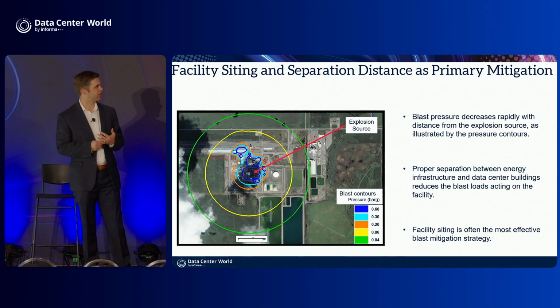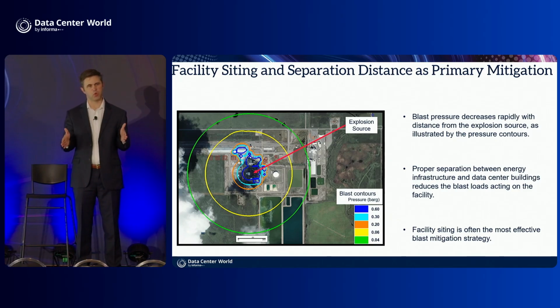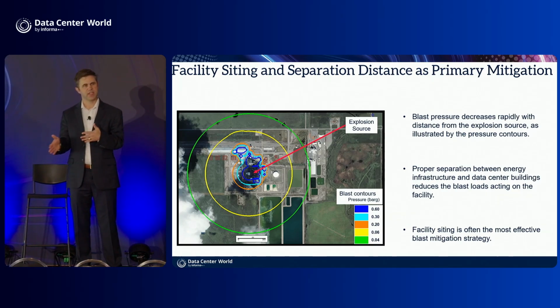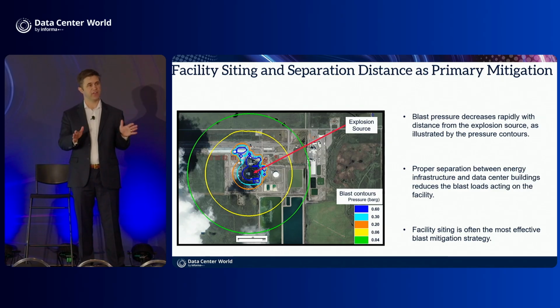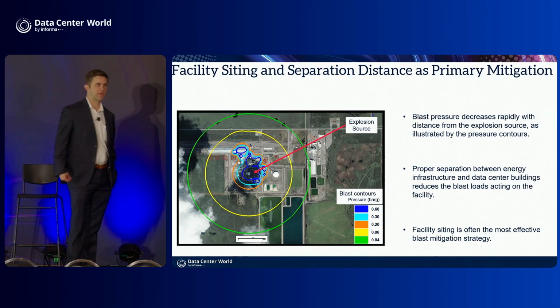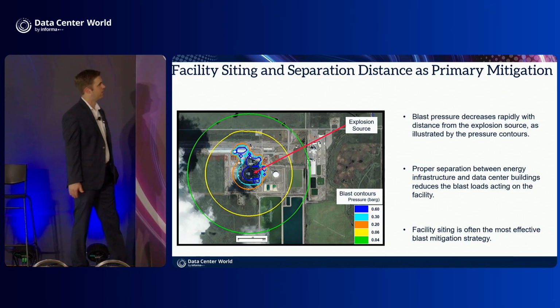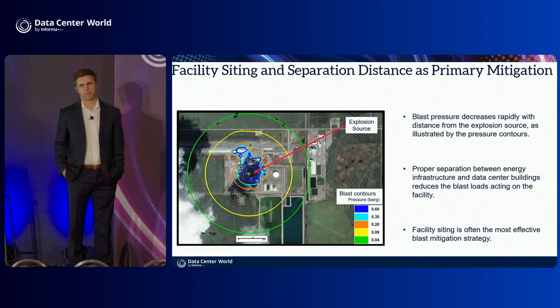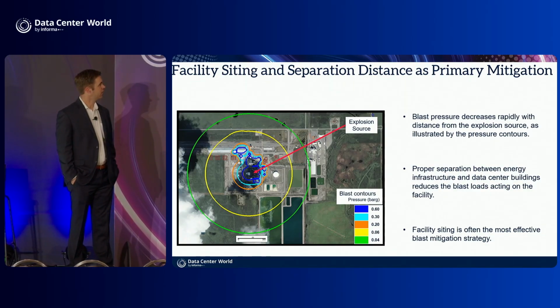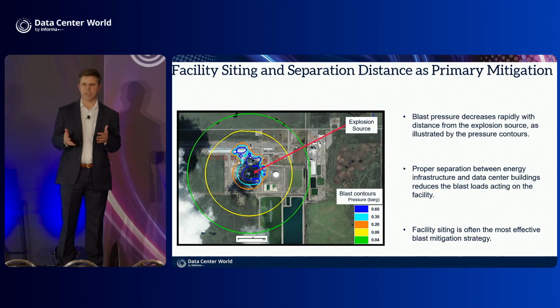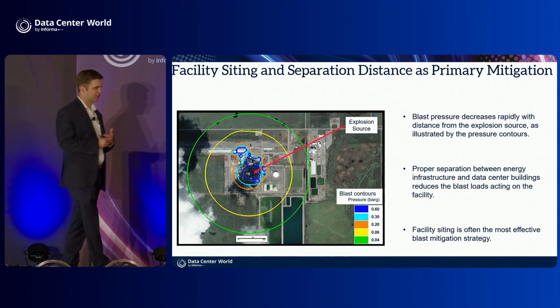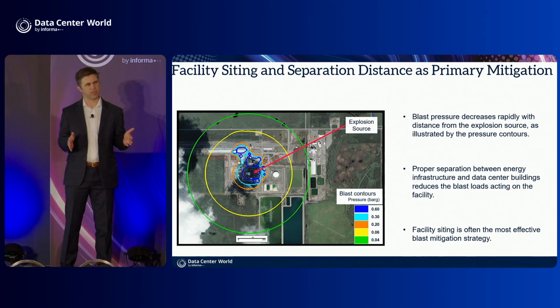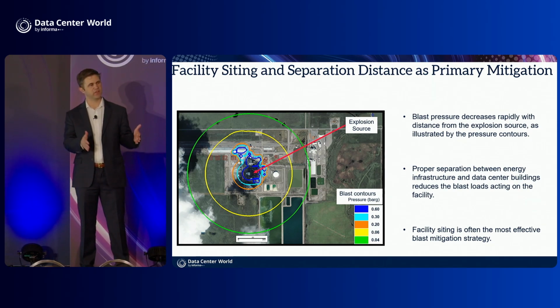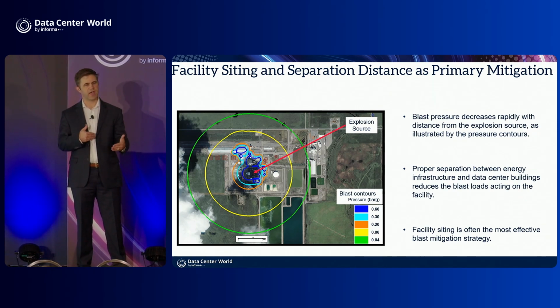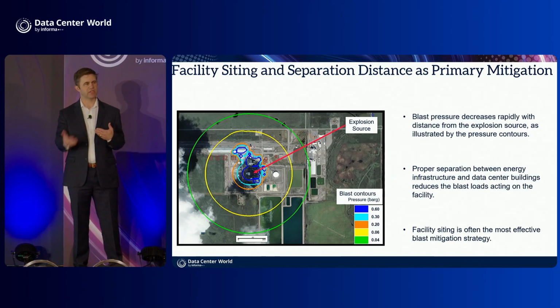The idea here is that creating distance between the hazard and what you're trying to protect is your best means of protection. Same idea as a terrorist threat: if you can put a fence between you and the bad actor, that's the best way to protect yourself. Applying that logic to a data center, providing offset between the generators or the BESS and the data center, even just 5 or 10 feet, could buy significant levels of protection.